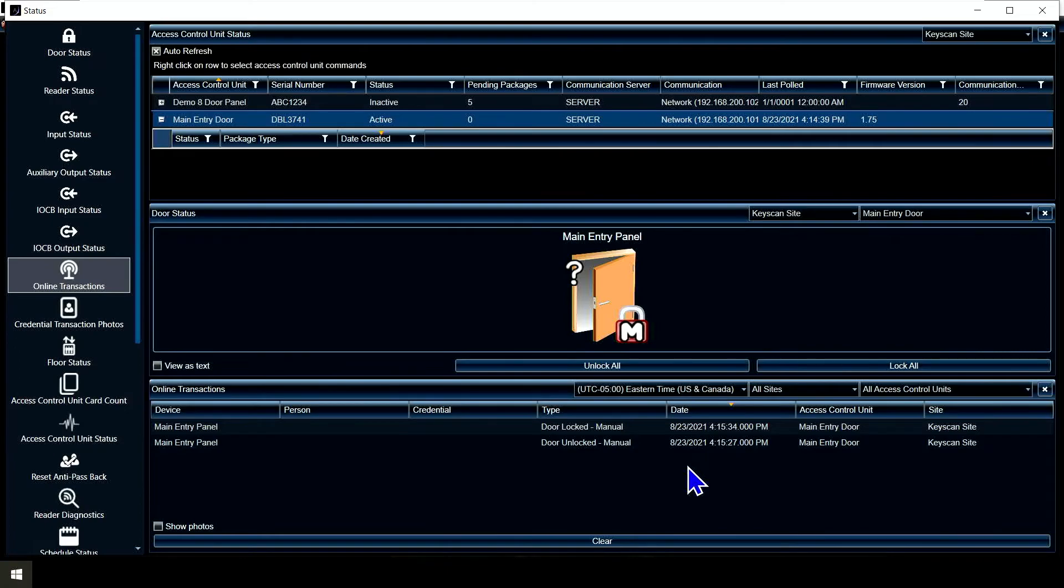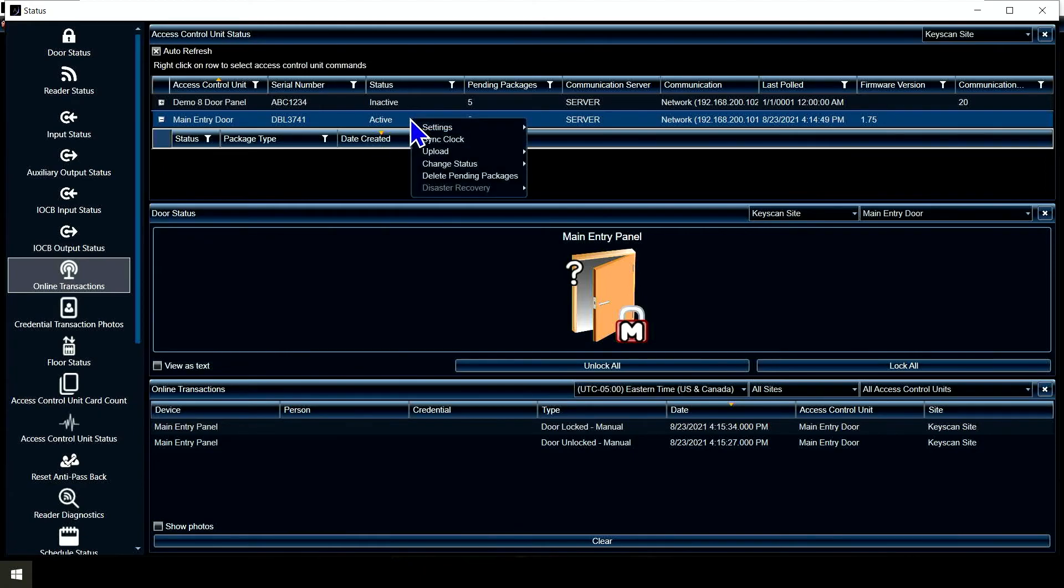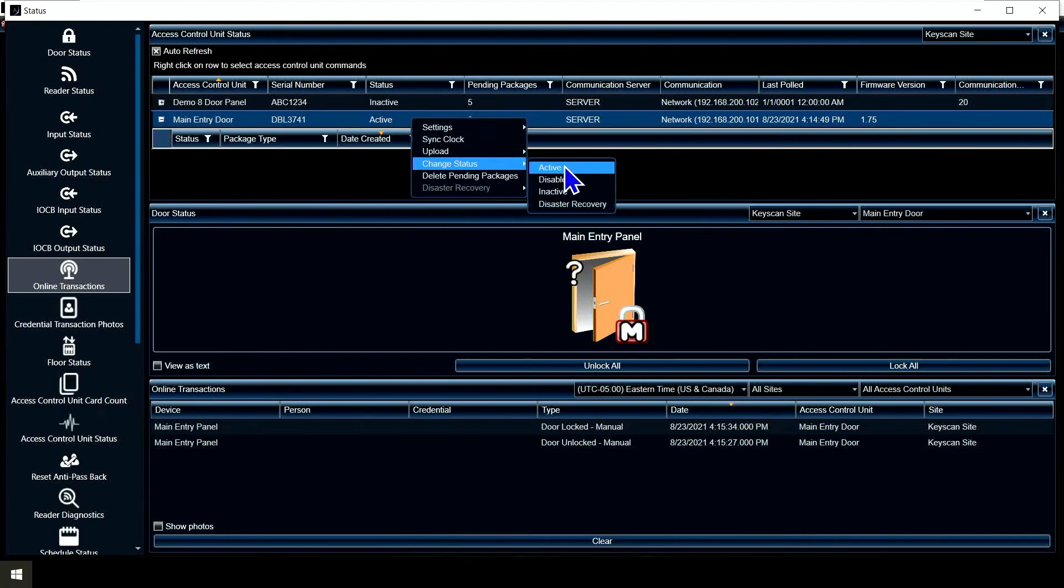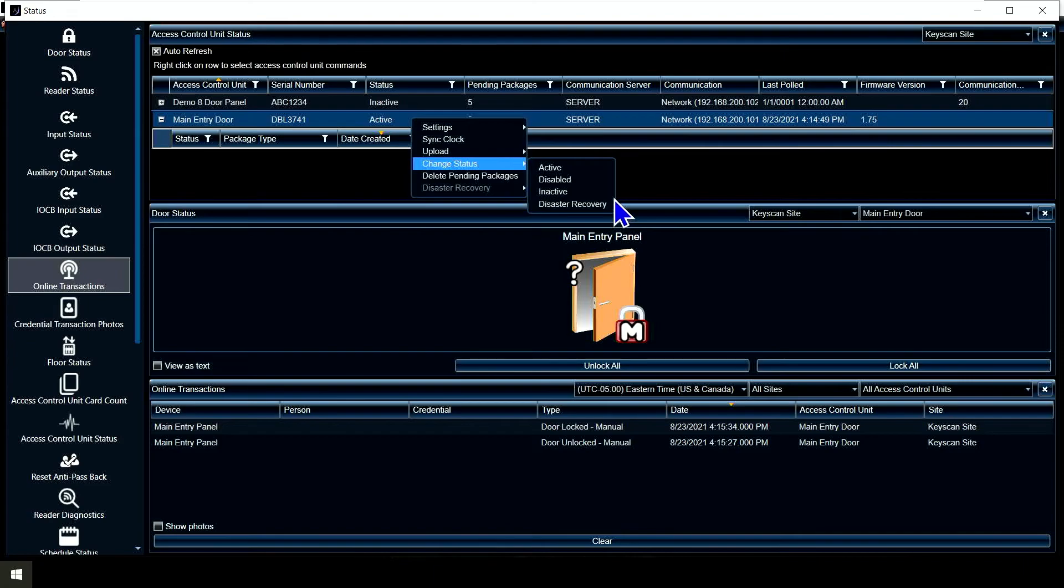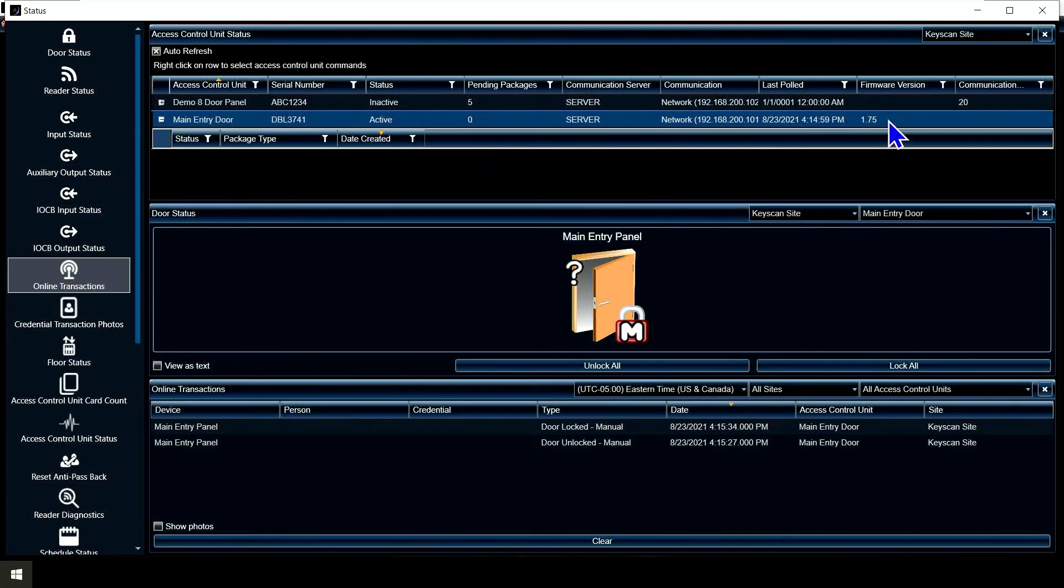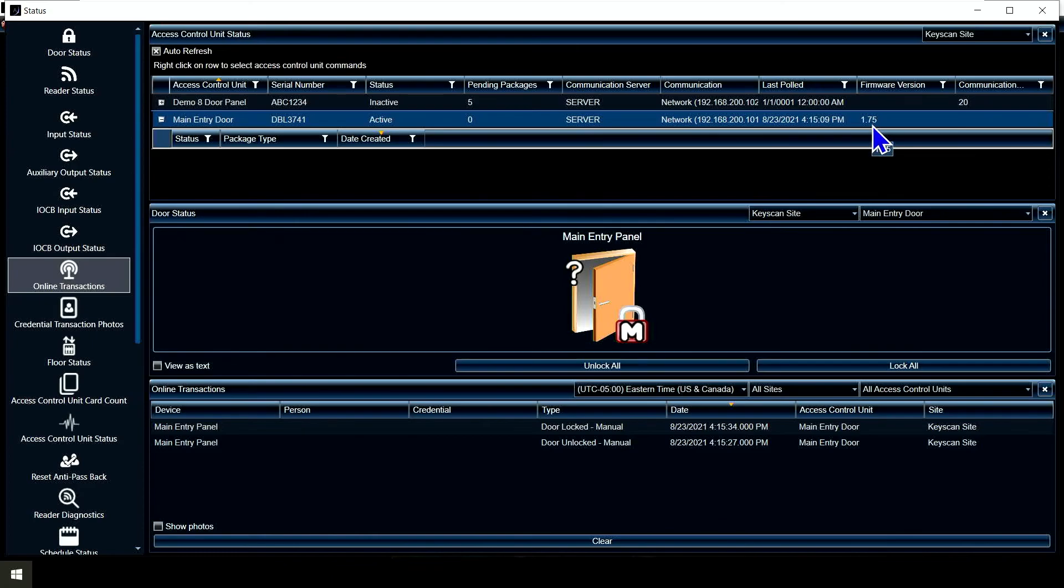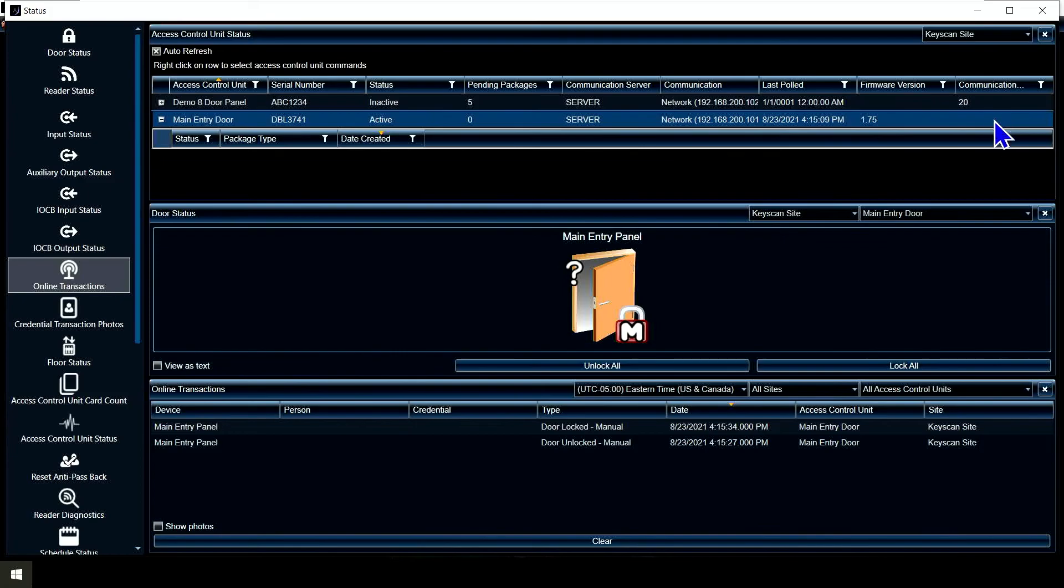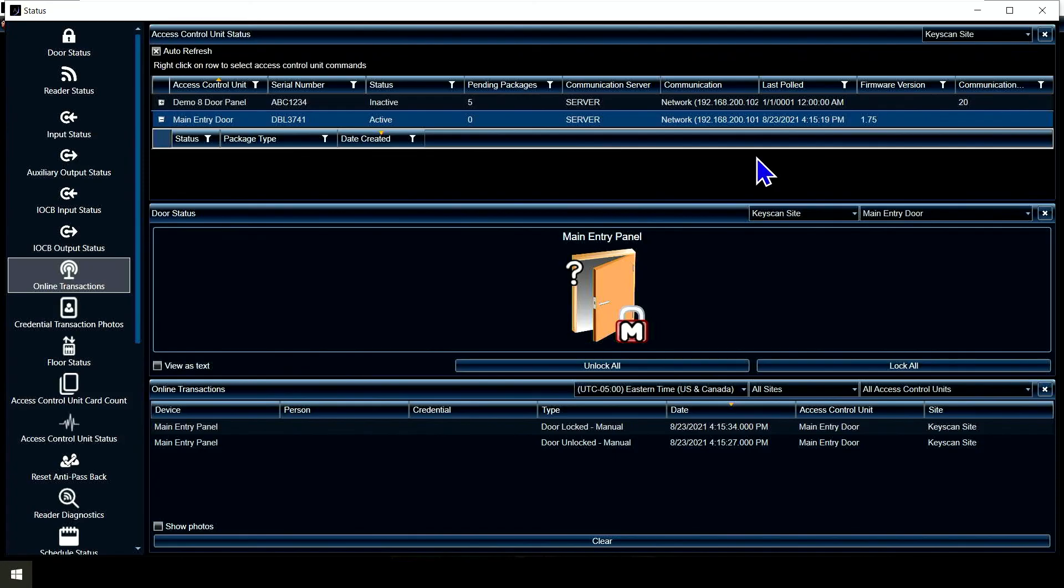Again, up at the top, what's our status for the panel? Active, inactive, disabled? We've got different options including disaster recovery, hopefully you're never dealing with that. Verify your firmware versions are 1.7 something, that you don't have any communication errors over here, and it also shows your last poll time. So I know I'm live talking to the panel. Everything looks good here, we can move on. Thank you.